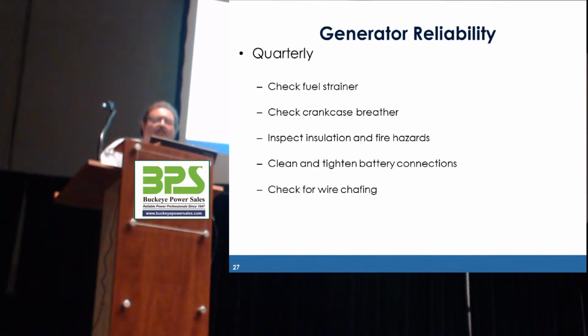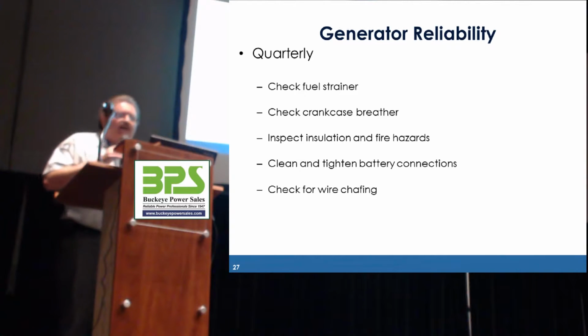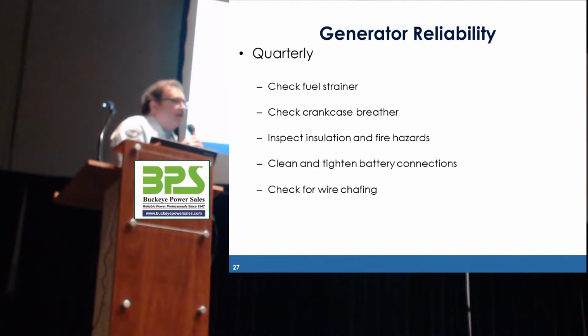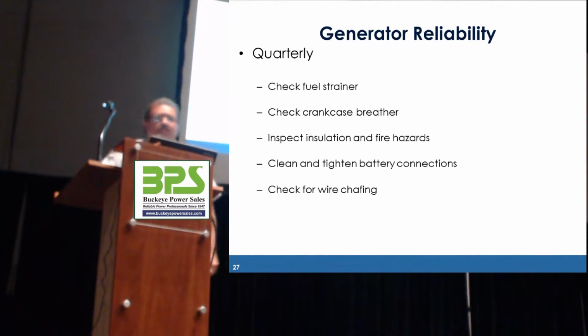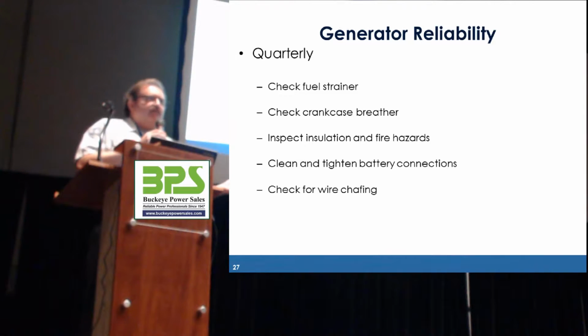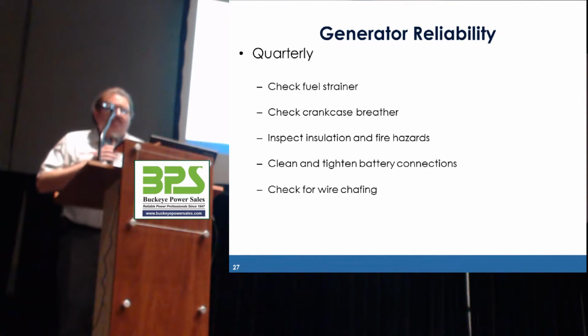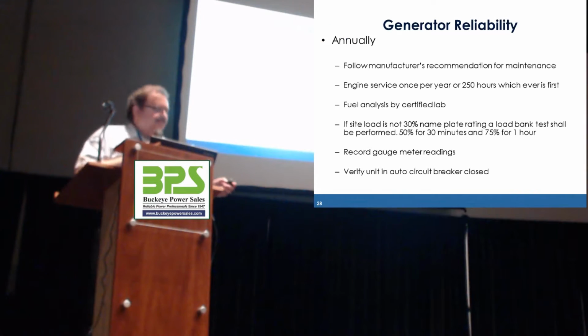We're supposed to do a visual inspection for any fire hazards. Clean and tighten the battery connections. So how do we do that? We have to take them off, which means we have to take the generator offline to do that, right? Because once you disconnect the batteries, the generator's going to be offline.